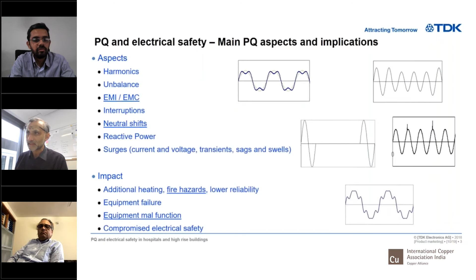Let's look at broad stuff—what happens to equipment because of these power quality parameters like harmonics, unbalance, interruptions, neutral shift. You get equipment damage, fire, sometimes even explosion, and definitely equipment failure. Failure could be not a normal failure, but in worst case scenarios an abnormal failure mode, which relates to reliability.